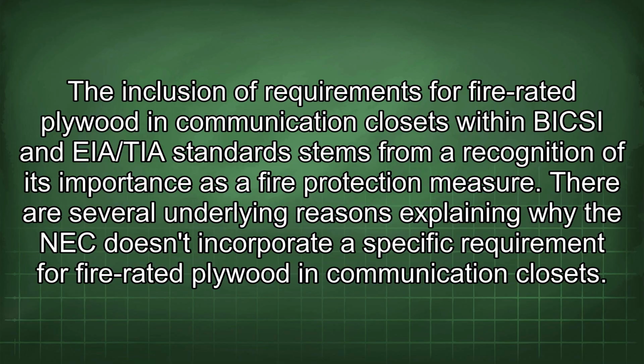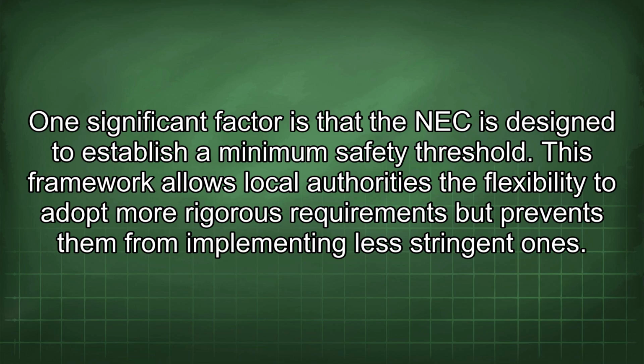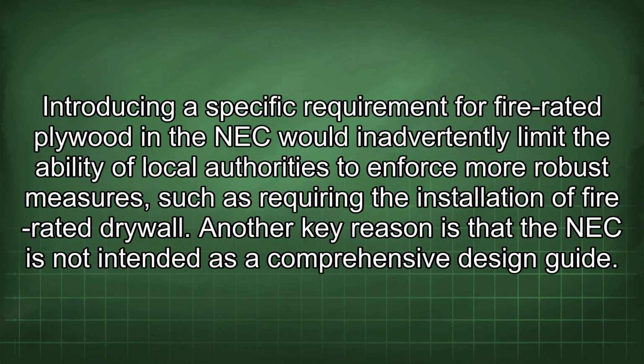There are several underlying reasons explaining why the NEC doesn't incorporate a specific requirement for fire-rated plywood in communication closets. One significant factor is that the NEC is designed to establish a minimum safety threshold. This framework allows local authorities the flexibility to adopt more rigorous requirements, but prevents them from implementing less stringent ones. Introducing a specific requirement for fire-rated plywood in the NEC would inadvertently limit the ability of local authorities to enforce more robust measures, such as requiring the installation of fire-rated drywall.